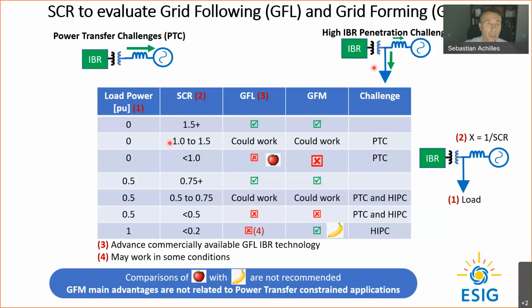So if we concentrate on the first 3 columns, which is what we are accustomed to talk about in the industry, this load is 0 megawatts, meaning that we're basically looking at this power transfer challenge aspect. If the short circuit ratio is more than 1.5, we could argue, depending on the technology, maybe a 2.5, but there is a value higher than that, grid following or grid forming technology are perfectly stable. There is a steady state point of operation that works, and there are many applications working in this way.